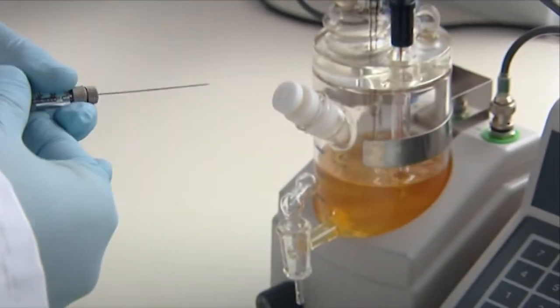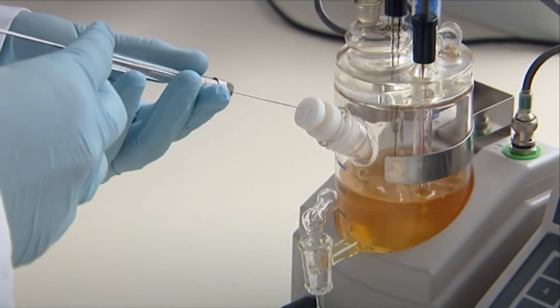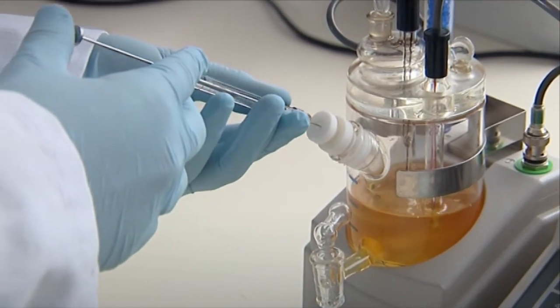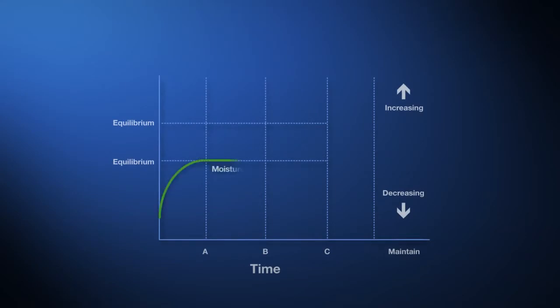The first test, moisture, is injected into the titration cell and we get a very accurate determination of the moisture down to 0.1 parts per million. The lifecycle of moisture on the degradation curve initially shows a very quick increase in the moisture as the oil tries to find equilibrium with its surroundings—that is, the materials within the tank but also the moisture within the atmosphere.